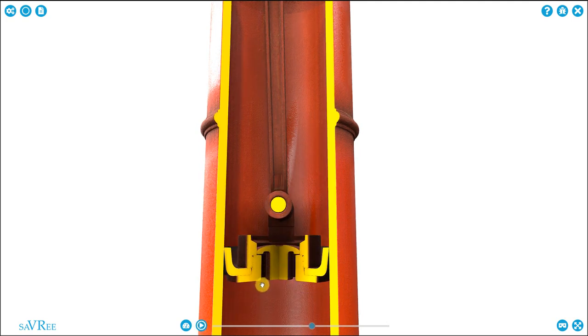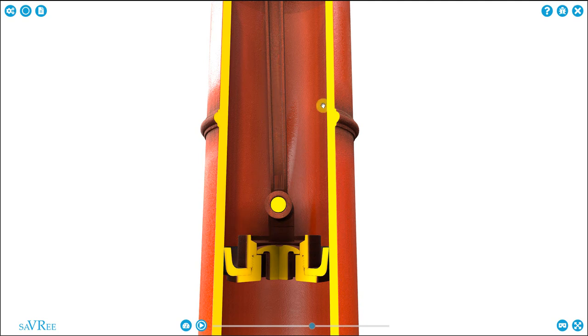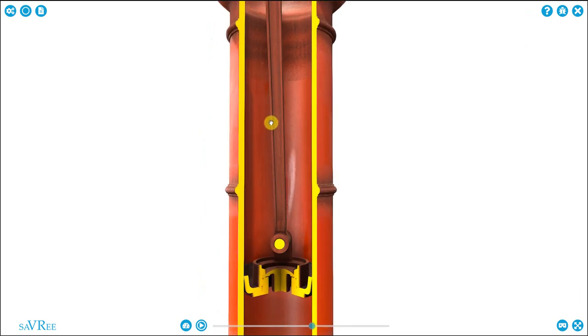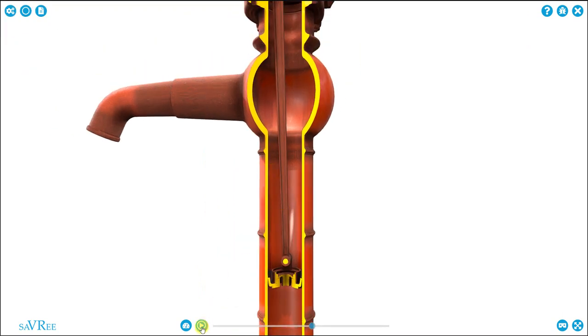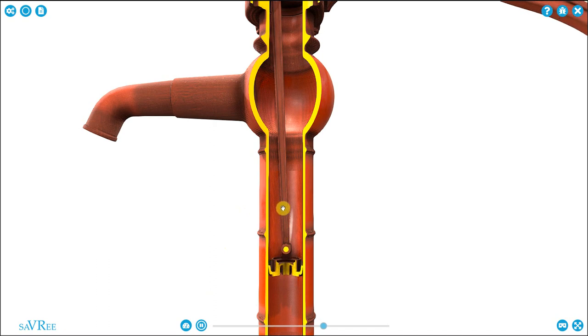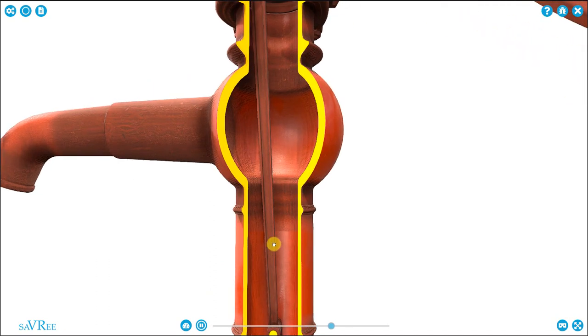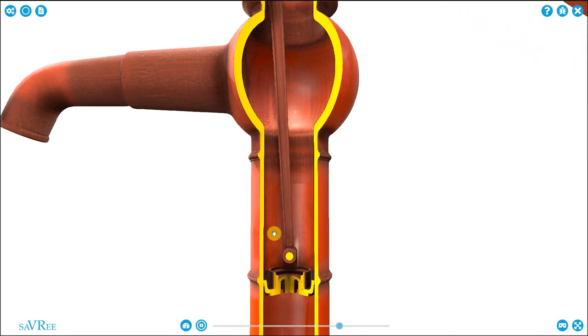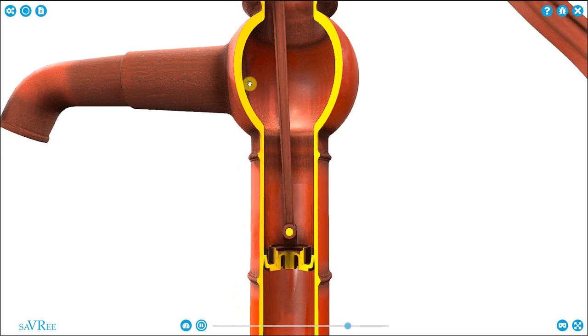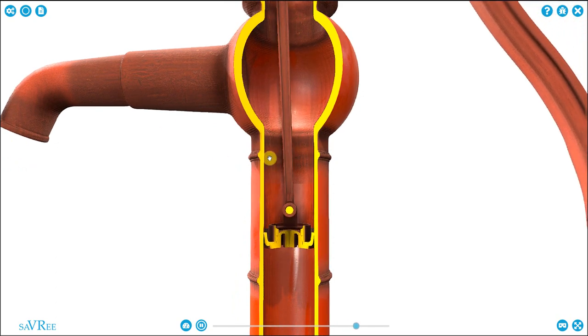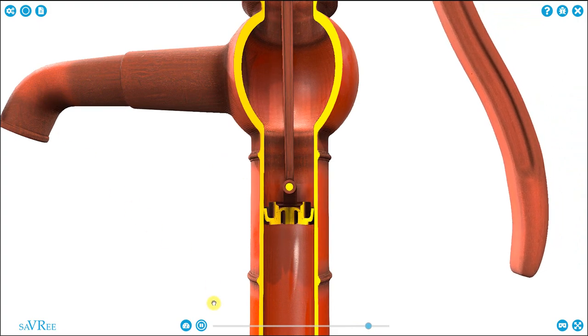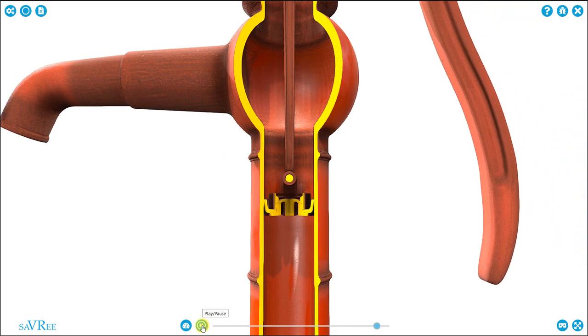And notice the piston valve is now closed. That happens just before we start to move our piston back upwards towards the top of the cylinder. So the fluid that we have now on the top side of our piston is going to be pulled upwards. You can see that in action. It's coming up, up, up. And if we had fluid here, it would be pulled upwards and then be discharged or would move up in height. And then it would just flow out of our discharge pipe. So that's essentially all that's happening.